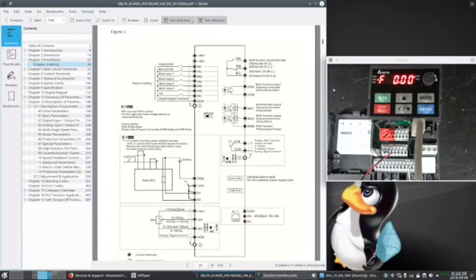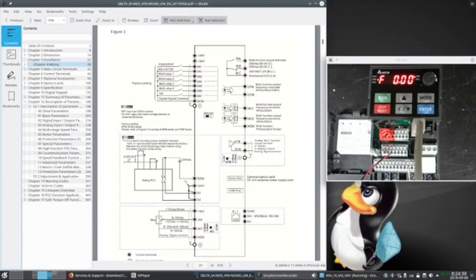The default configuration for MI1 is a forward command, with MI2 being the reverse command. Here they're switched to the DCM terminal. That's because of the position of the NPN PNP switch, which I believe defaults to NPN.